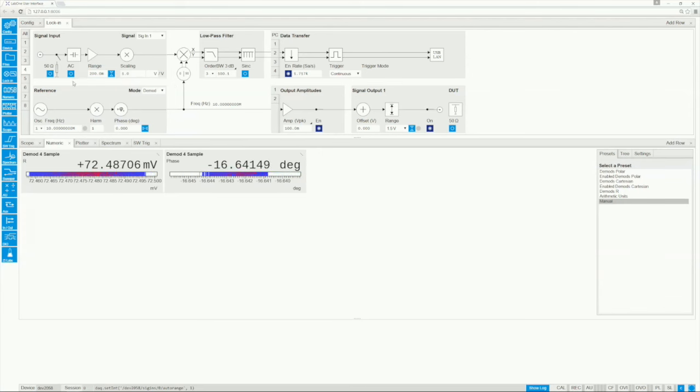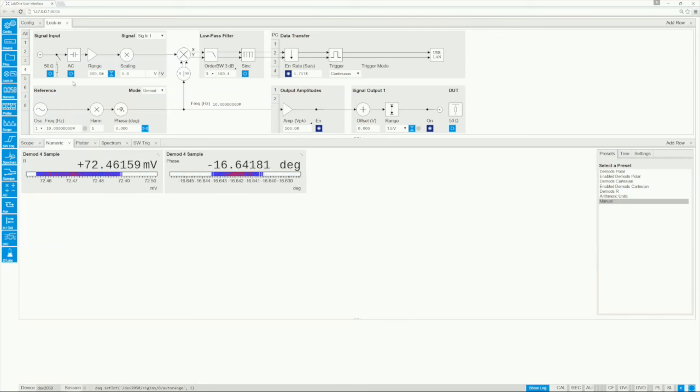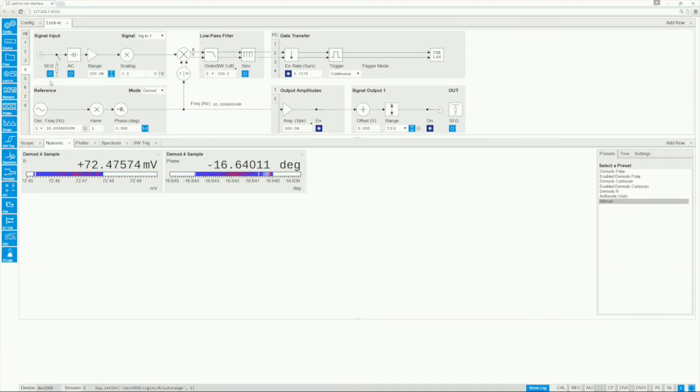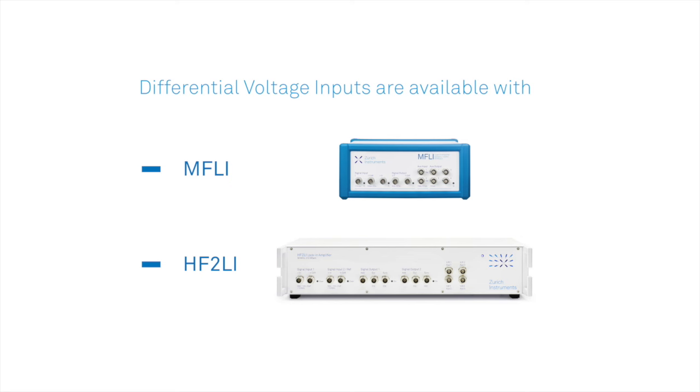It is very important to avoid any signal clipping which can cause detrimental artifacts. The other input controls select between AC and DC coupling, high impedance or 50 ohm input impedance, and depending on your lock-in, single or differential measurements.